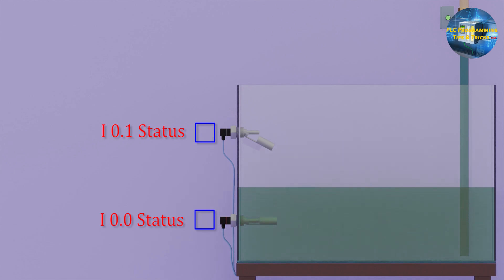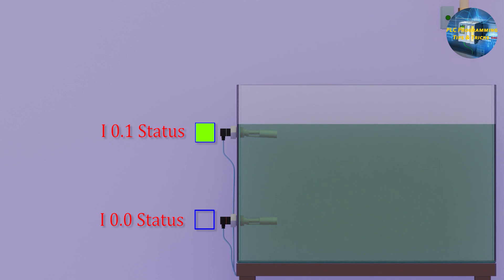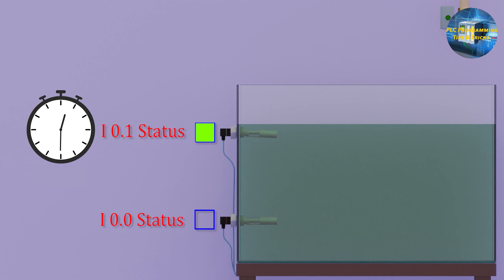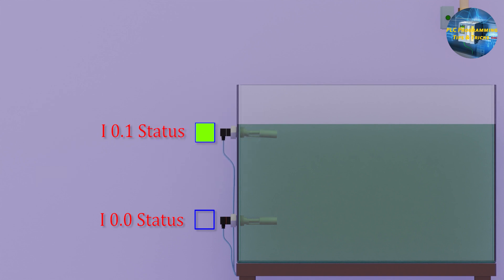These up and down movements of the probe send many pulse signals to the PLC input. To filter the signal and get a stable input signal from the probe, we use a timer after the sensor signal, so that if the water probe signal is continuously on for 500 milliseconds, only then will we consider this stable signal as true. We already made this logic in the sensor block in the last video tutorial.